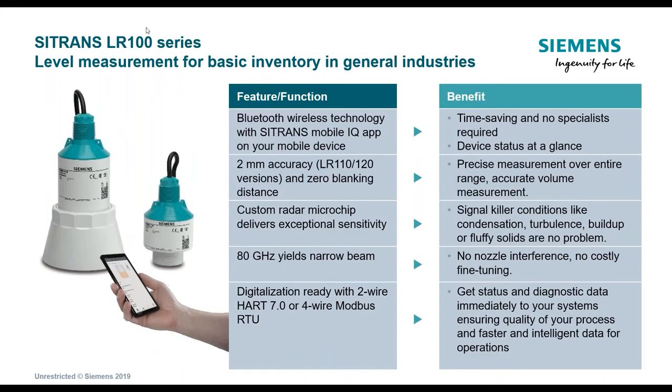Reviewing the features and functions: Bluetooth wireless technology with the SITRANS mobile IQ app on your mobile device. The hope is that it saves you time — you don't need any special instruments, a third-party handheld, or software to program the unit. Higher accuracy allows measurement over the entire range with zero blanking distance. This custom chip should allow you to configure the unit one time without any later fine-tuning. The unit is capable of digitalization as a two-wire HART 7.0 device, and also available with Modbus output.